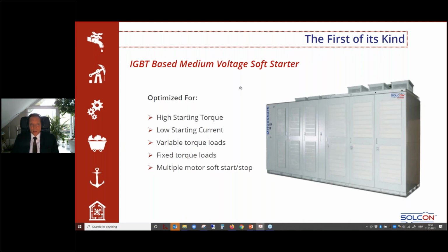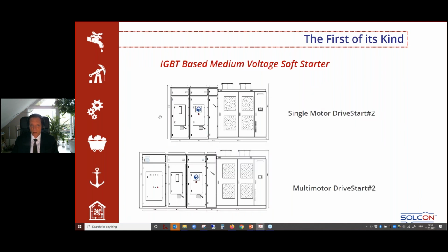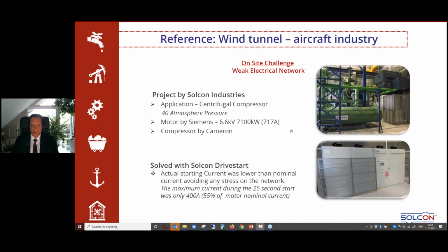So again, IGBT based medium voltage soft starter is optimized when you need high torque at a low starting current. It's available for variable torque loads like pumps, compressors, fans, but also for fixed torque loads like mills or extruders, and you can do with it multiple motor soft start and soft stop. Here you see again the outline of a single motor drive start where the switchgear portion is connected directly to the VFD portion, or multi-start in this case, where you have here also the SCR starter connected to it.